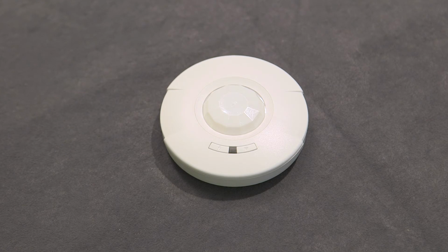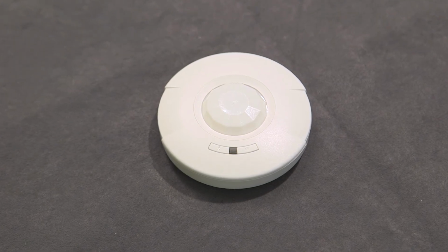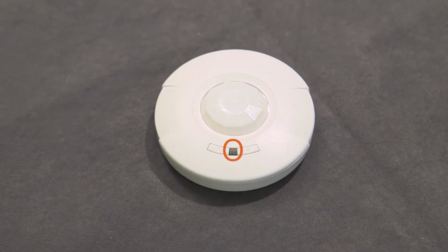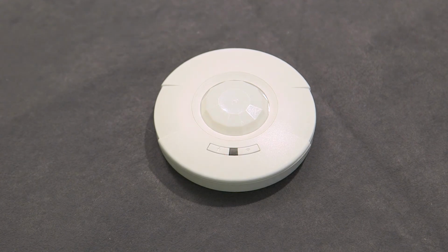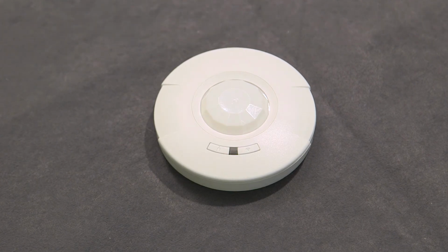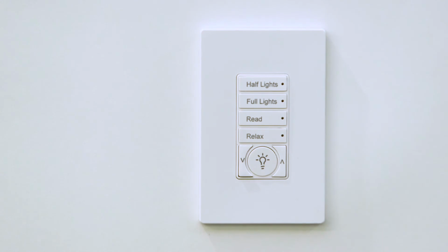Next, verify the battery-operated ceiling sensors. Confirm that the red LED next to the sensor window flashes approximately once every 10 seconds. Lastly, verify WaveLinx wall stations.